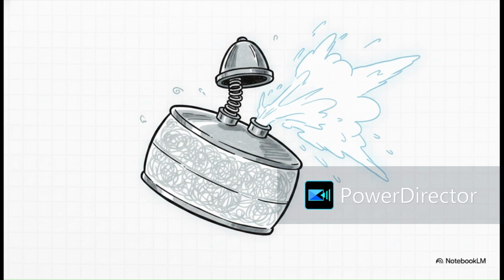The PRV is basically a heavy, spring-loaded safety lid that automatically pops open at a set limit to safely release that explosive pressure. So the crucial point is this: if a PRV pops, it means something violently went wrong. You never ever just reset it. You absolutely must investigate why that pressure spiked in the first place.